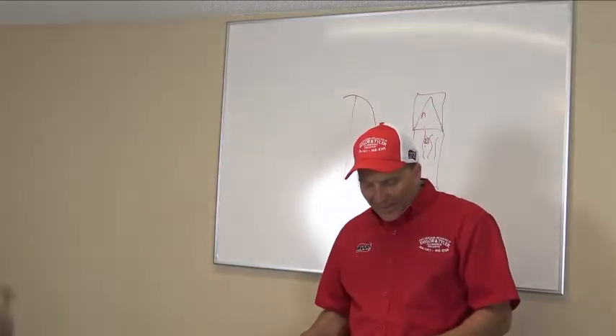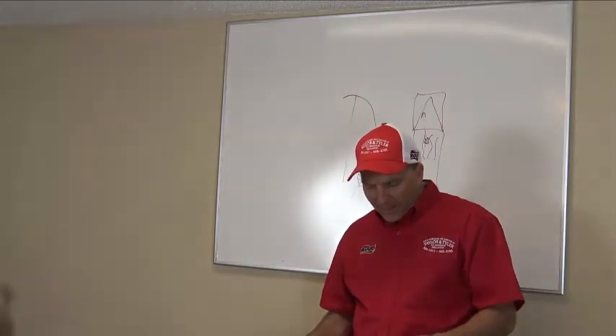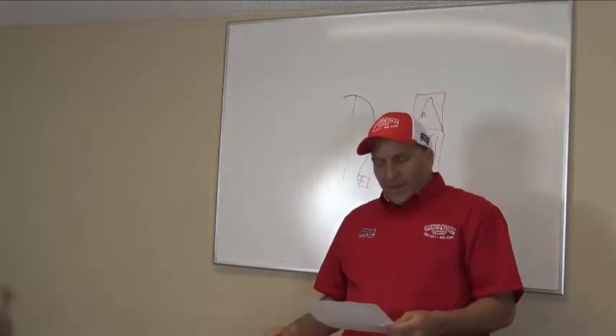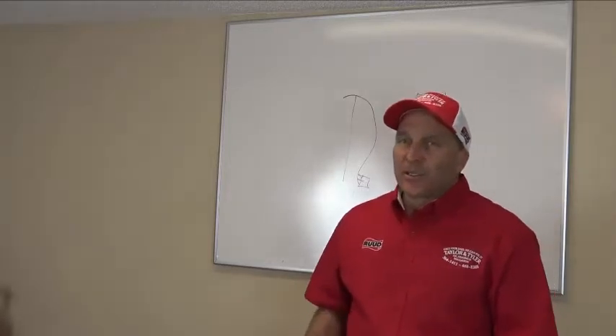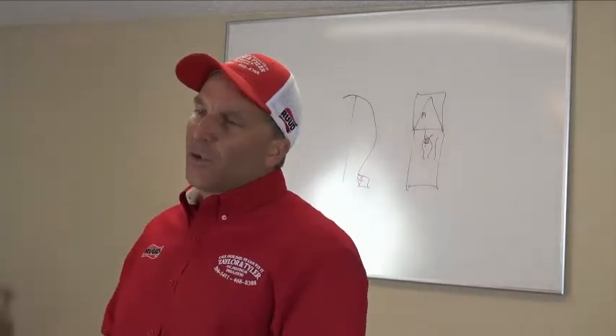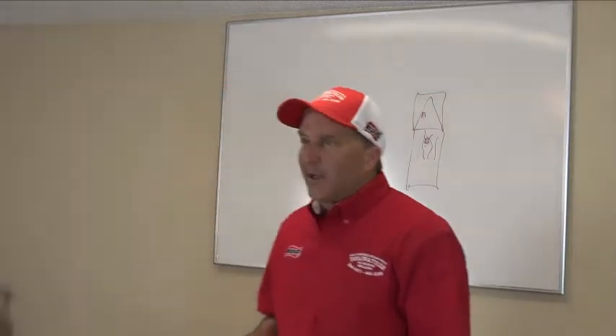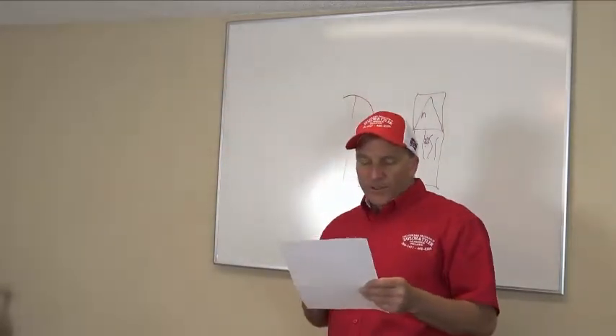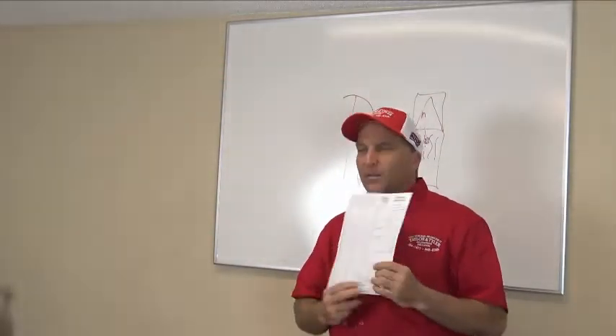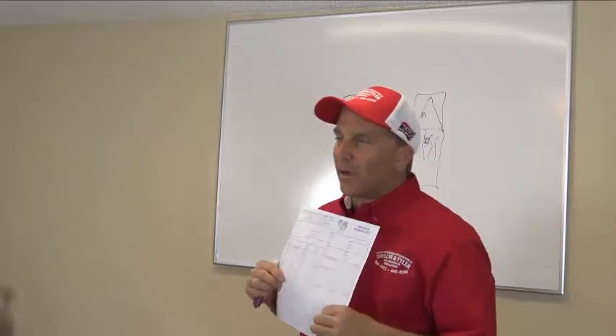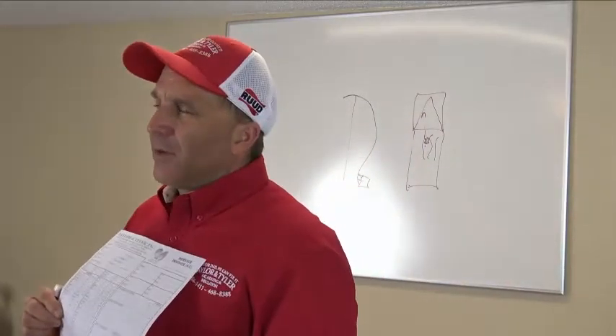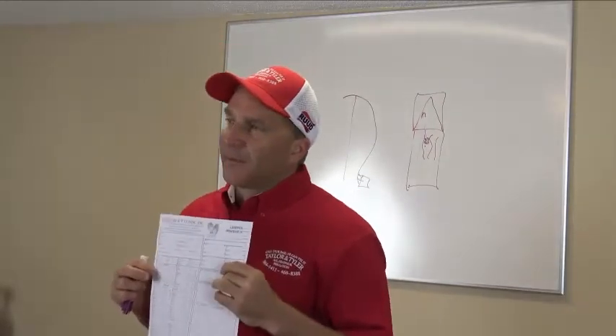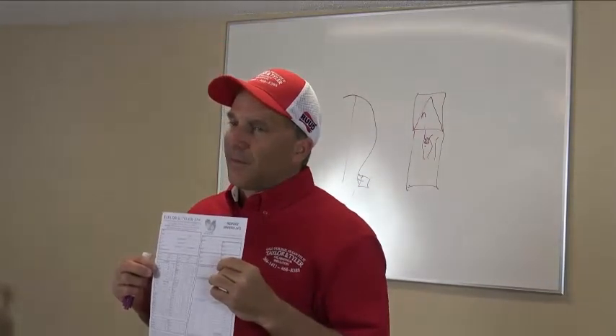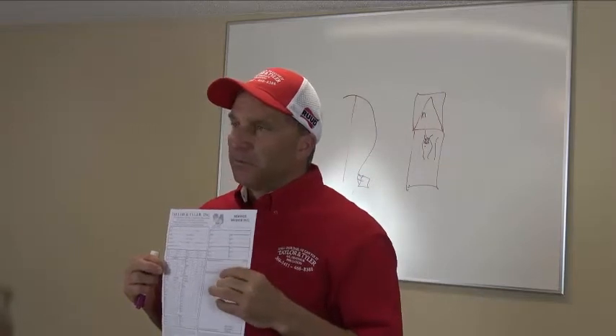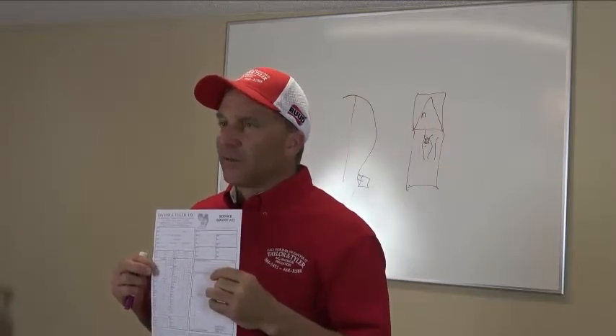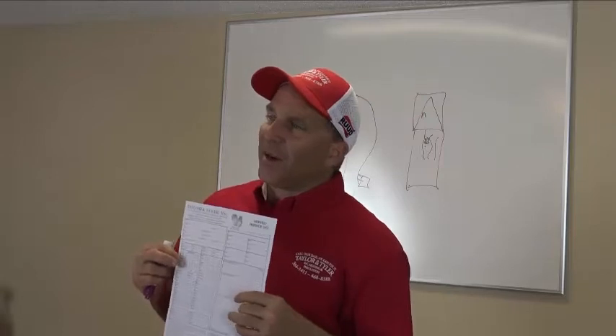So, refrigerant leaks, none, visible, undetectable. Okay, you write your head pressure, your suction pressure down, your superheat down, your subcooling down, and you put on there refrigerant leaks, none. And you got down at the bottom here, R22, $180. Wait, you told me refrigerant leaks, none. You put undetectable. Did you recommend a leak search? Did you say anything about it?